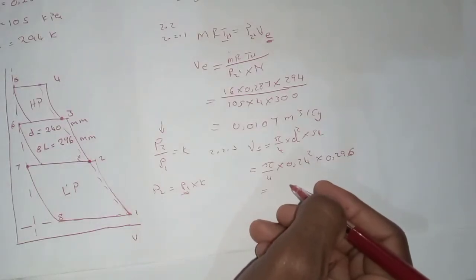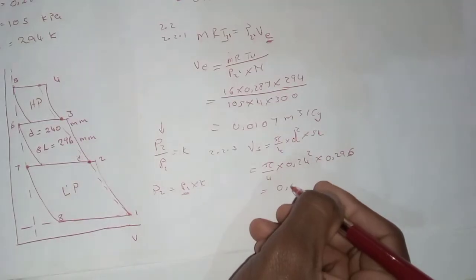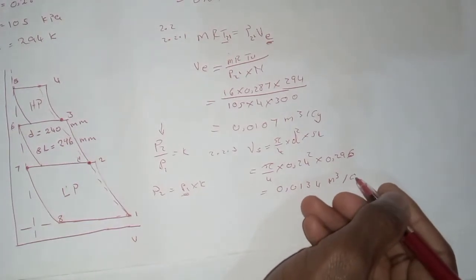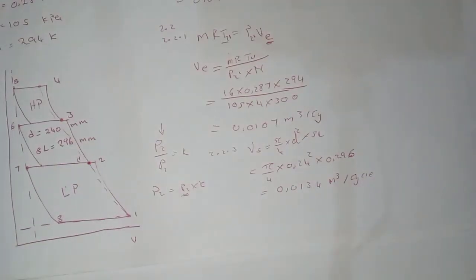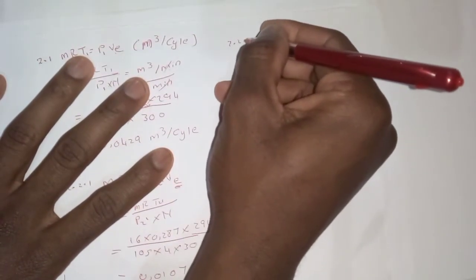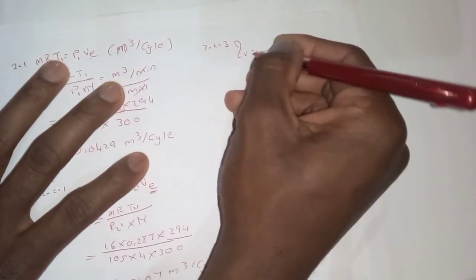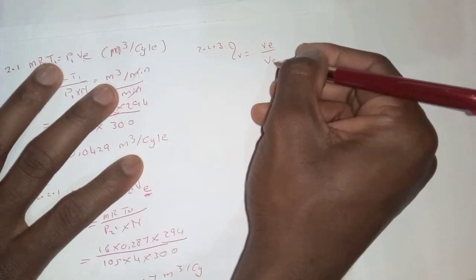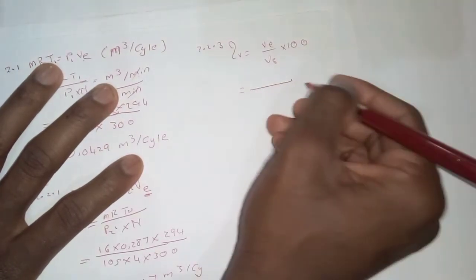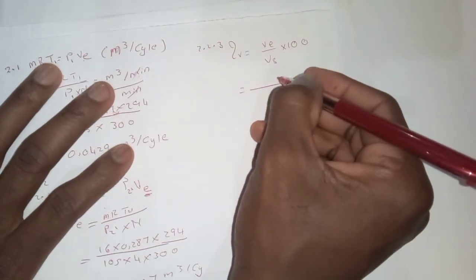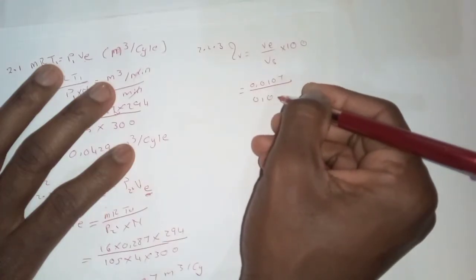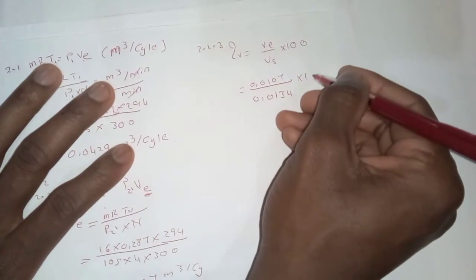For 2.2.3, the volumetric efficiency — it is given by the effective volume divided by the swept volume times 100. The effective volume is 0.0107 and the swept volume is 0.0134. Multiplying by 100 gives a volumetric efficiency of 79.85%.